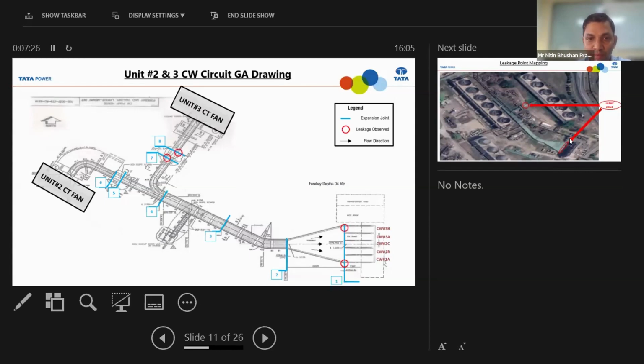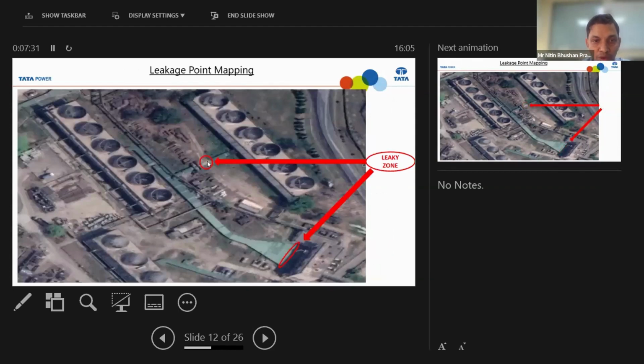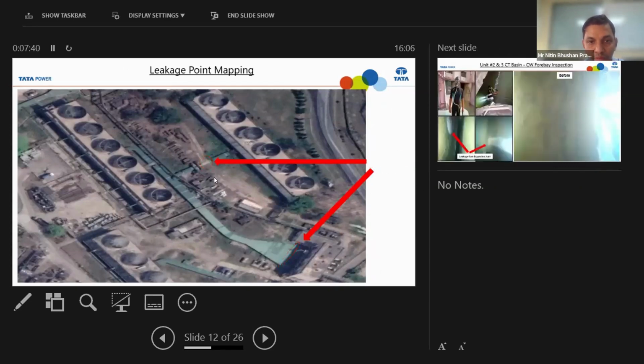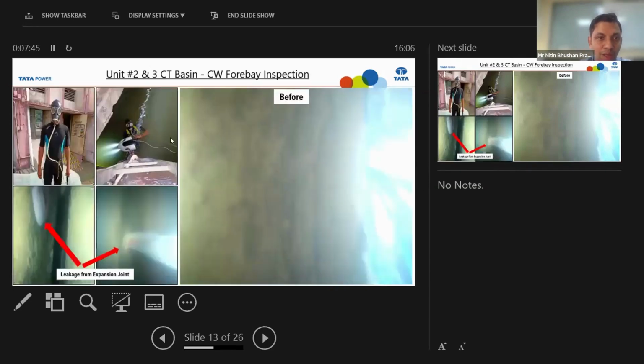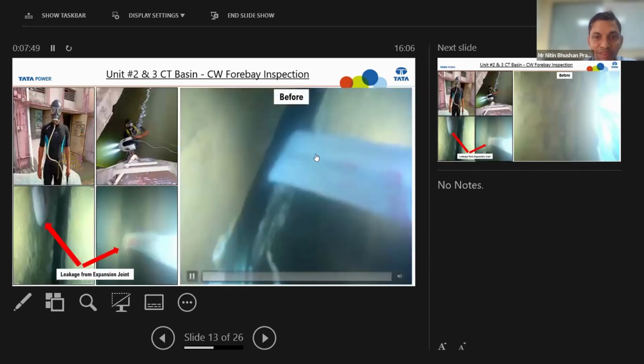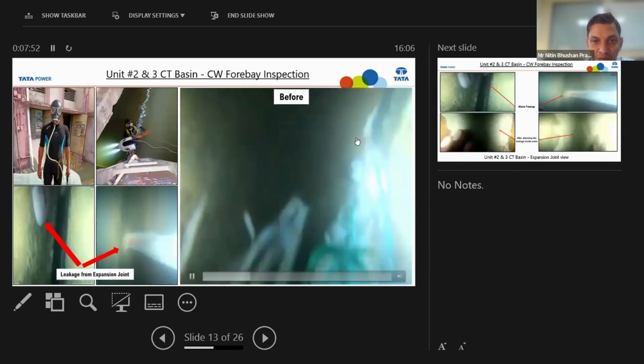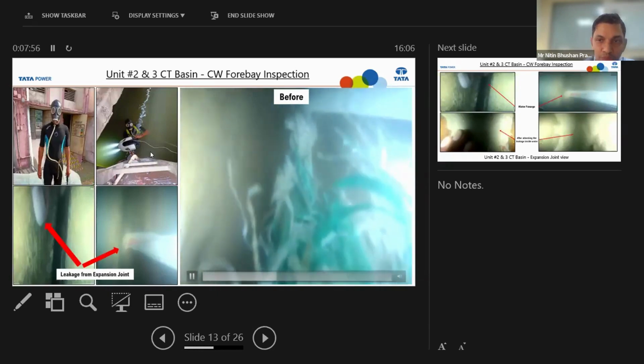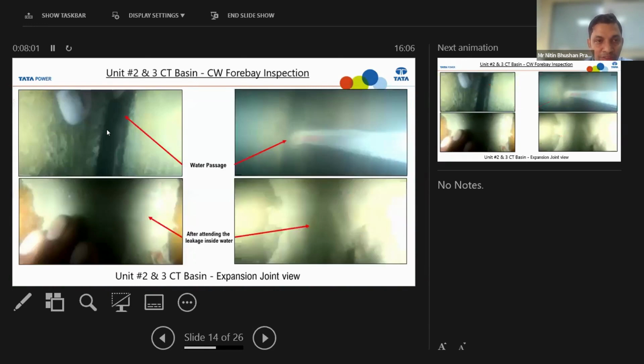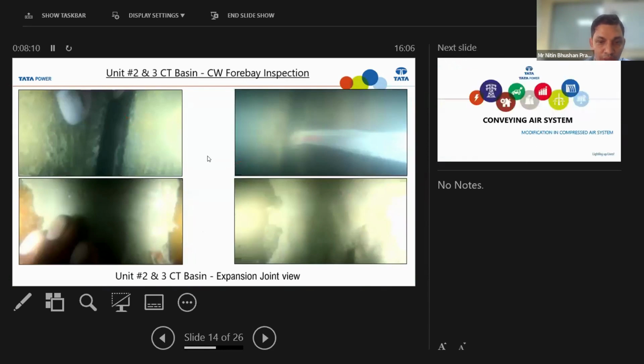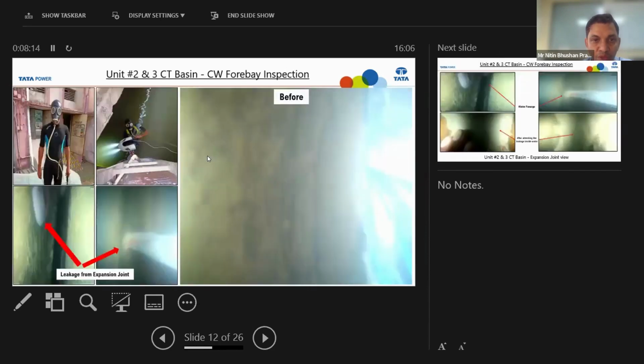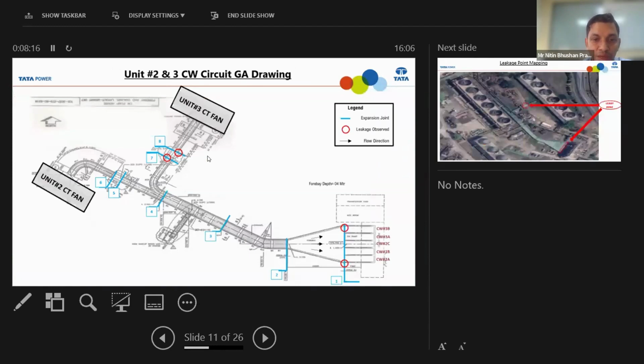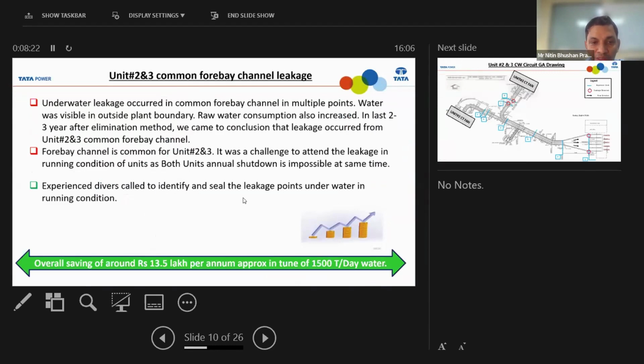This is the aerial view of the cooling towers and the forebay. You can see in this aerial view that in these expansion joints, the leakages were there. This is the live video when the divers have gone inside, and you can see in the video clear-cut what kind of leakages are there inside. This is the water seepage inside the expansion joints, which later on we have attended. And with all this system leakages, we had an overall saving of around 1500 tons per day of water, and a total saving of 13.5 lakhs per annum in this process.